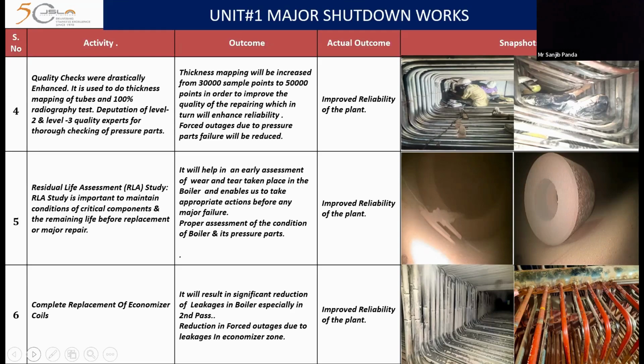Then complete replacement. This is one major activity we have carried out. Complete replacement of economizer coils, consisting of around 250 coils, in both of the boilers we have done, and this was one of the major causes of our reliability issue, because of tube leakages and all that. We were facing reliability issues, which have been addressed significantly. Next one.